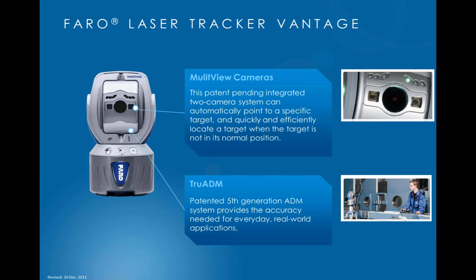The MultiView cameras are a patent-pending integrated camera system which allows us to bring up on our computer screen a visual of what the laser tracker can see. If we have a series of reflectors in an area—for instance, doing a repeatability study with several reflectors glued onto a moving part—we can, from the comfort of sitting behind the laptop screen, tell the tracker which reflectors are in the field of view that we want to measure. It will lock onto them, take a measurement, then move to the next one, and we survey them all. Then we get the robot or moving part to execute its move and come back, so we can verify whether it's repeating or whether there's a shift in repeatability when it executes a command.